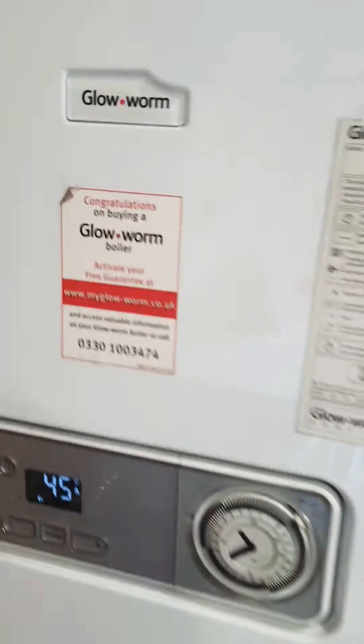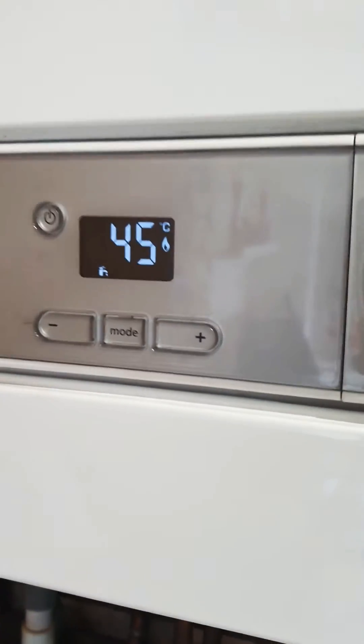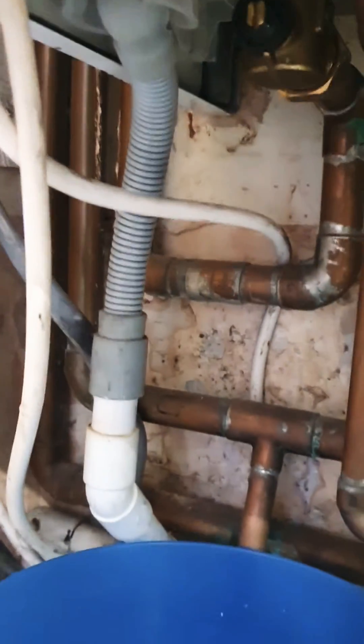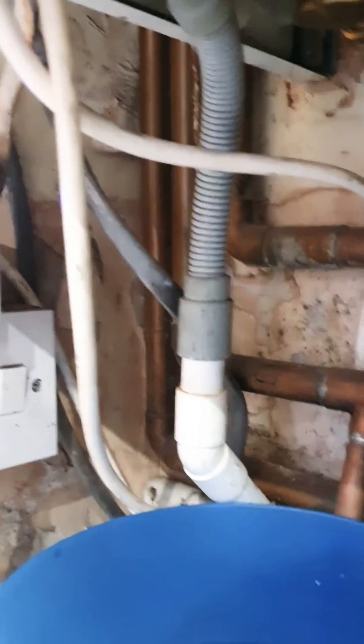This is the Glow Worm Betacom. I've been having issues with it firing up and it was showing an error code of F28, usually failing to ignite due to the condensate pipe — this one here — failing to ignite because that's frozen up outside.